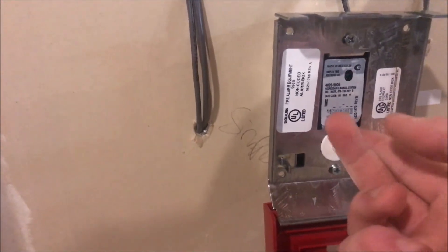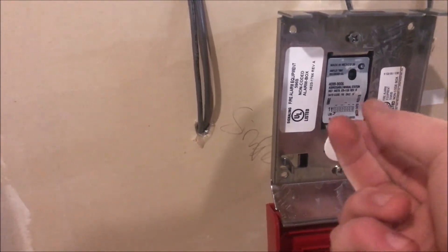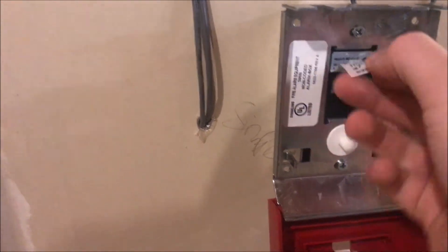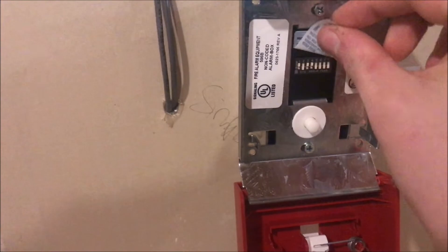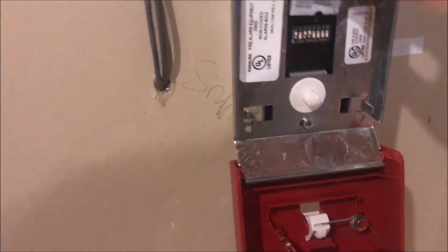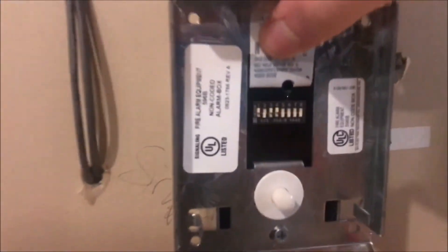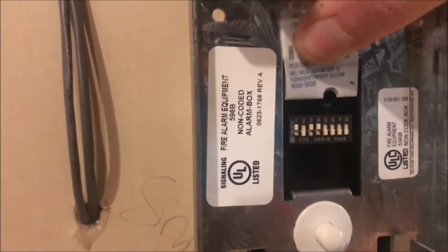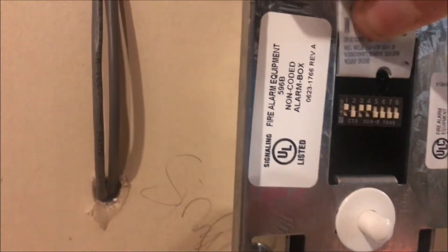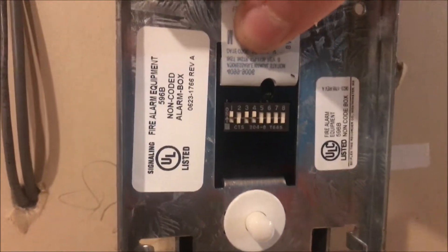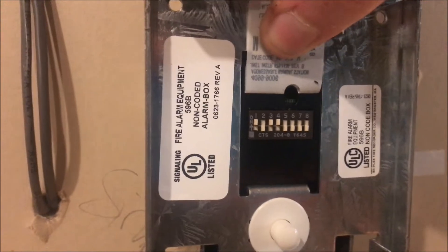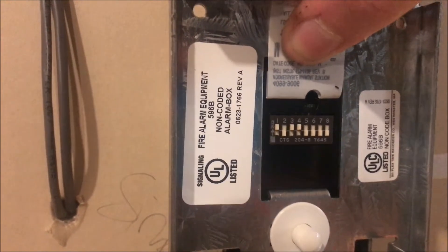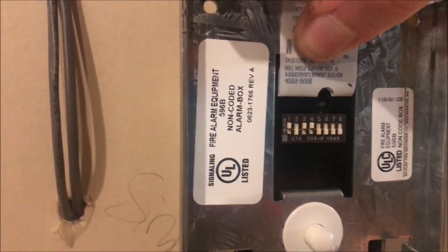So under here, this is a 4099-9006 addressable dual action pull station. Under here there are a series of dip switches that follow binary code. Right now mine is set to 13, and you do this by adding up to get to the number.